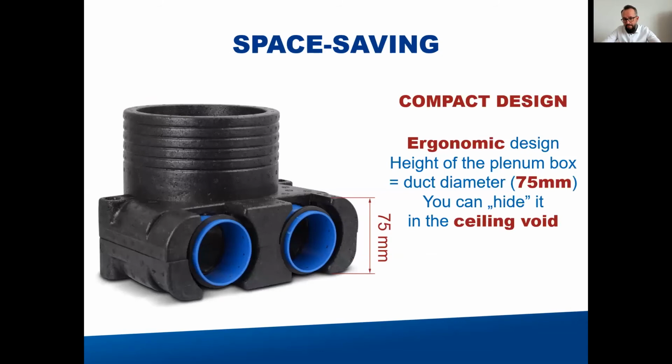The main part of the box is only 75 millimeters high. This is the height of the outer diameter of the duct. So if you want to hide it in the ceiling or in the insulation layer, you don't have any additional millimeters above. It's only the height of the duct, and the height of the plenum box is 75 millimeters. That was also the idea that drove us while we were creating this product, to have a very low height so that it is possible to hide it, as I said, in the ceiling, in the insulation, also in the concrete layer if required.